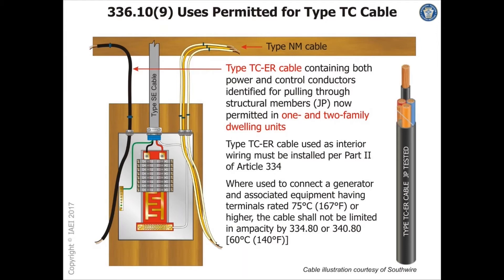Type TC-ER cable containing both power and control conductors that is identified for pulling through structural members is permitted to be installed in one- and two-family dwellings. There are suffixes for the cable that explain those permissions.